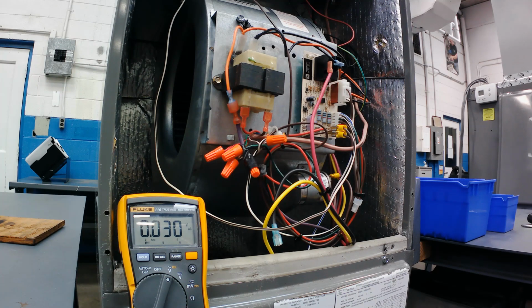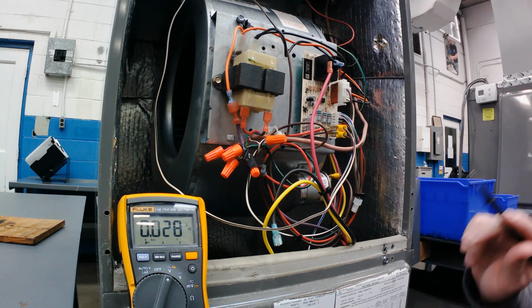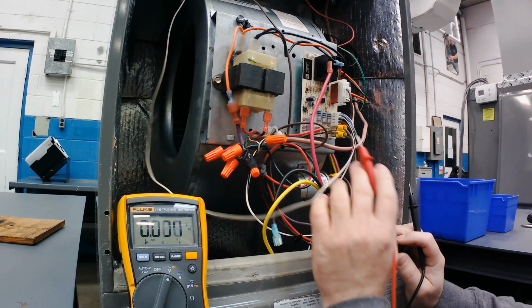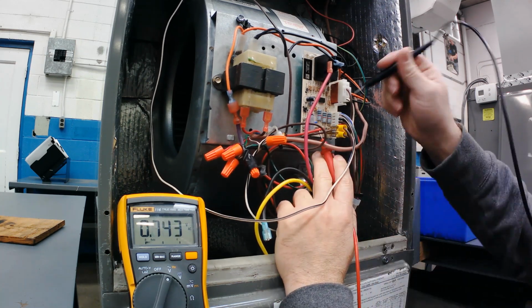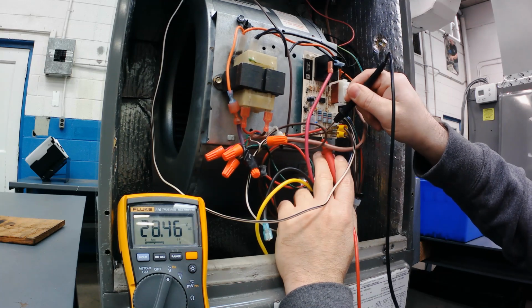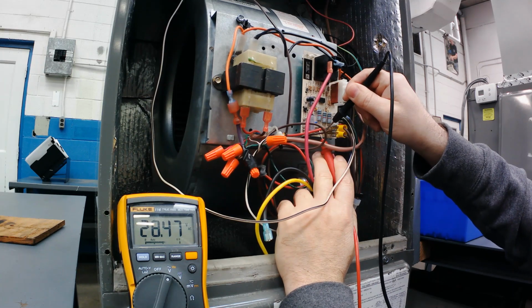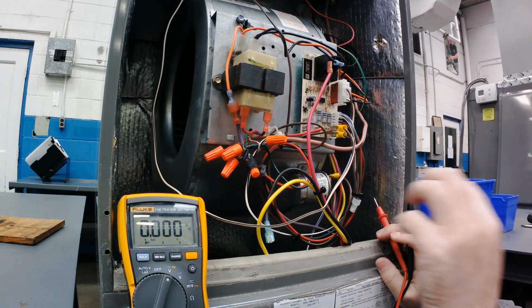It doesn't have to have power on some boards, right? It doesn't have to have power to necessarily let something flow through it on a normally closed switch, but in order for that brain to think and perform its function, it's going to have power. So first things first, you always prove power. We're always looking for power on electrical problems. So I'm going to do the transformer R to transformer C. Okay, and you can see there I've got 28 volts. So we have power to the board.